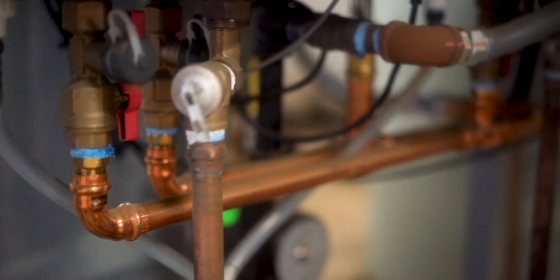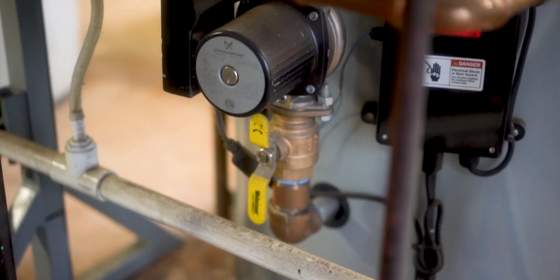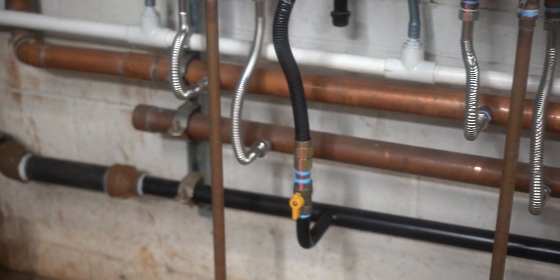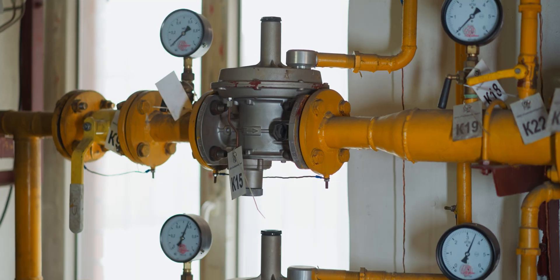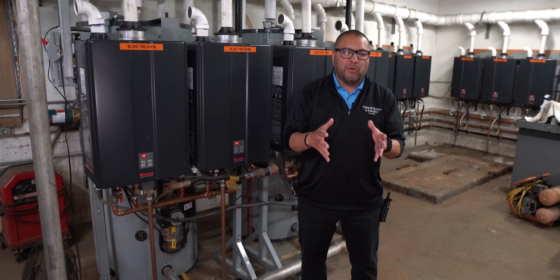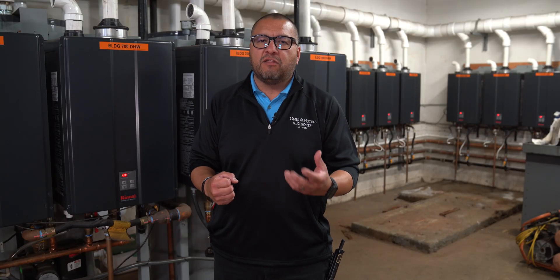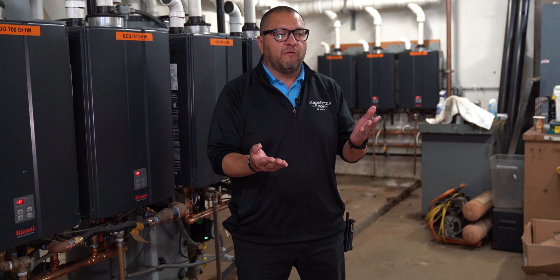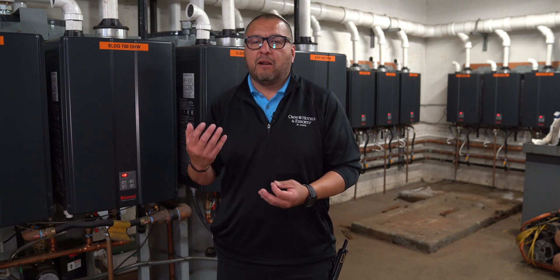Can you talk about the results you've seen since installing the Rinnai units? The savings from a BTU, from a therms, from a cost perspective have been amazing. I was crunching the numbers for a trade show in Atlanta, and I had to do the numbers multiple times because I couldn't believe what I was seeing. Comparing 2019 to 2022, which were very comparable from an occupancy perspective, and this particular building is on its own gas meter — so these are close to real numbers. To save 120,000 therms in that first year at a cost of $1.11 per therm resulted in savings of about $135,000.